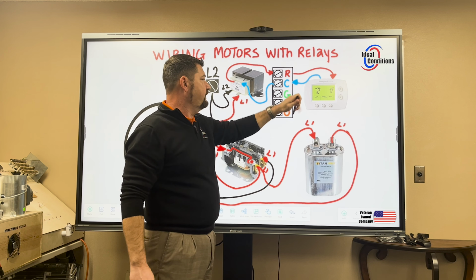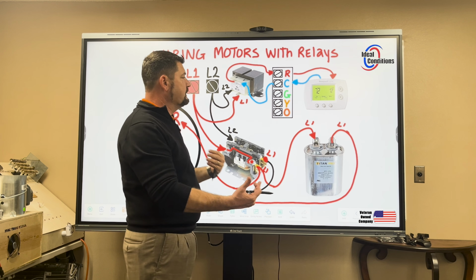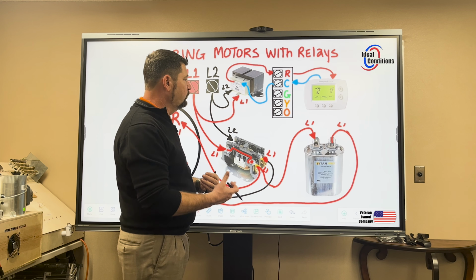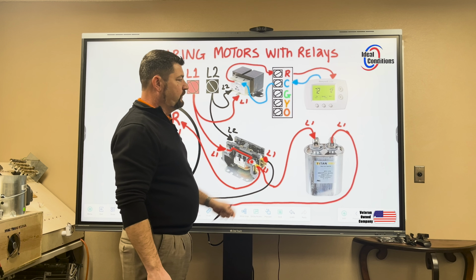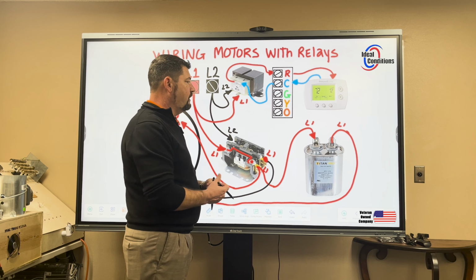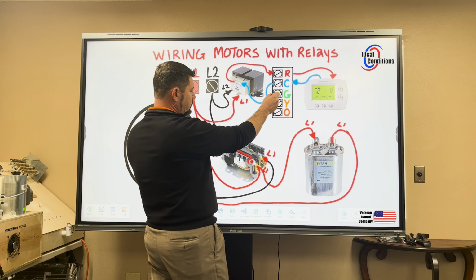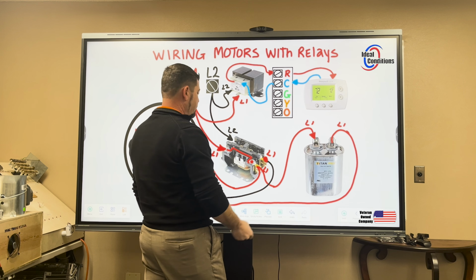Input here, then back out, back to the transformer. So there's my path, and now my first load can energize, and if there's a call for cool, heat, or just fan on, that thermostat's typically always going to energize the G call with any one of these three combinations.